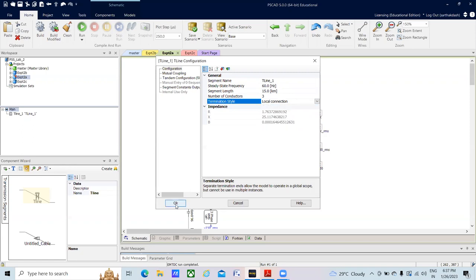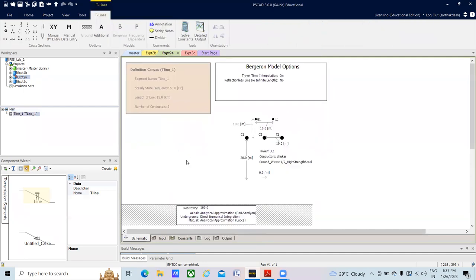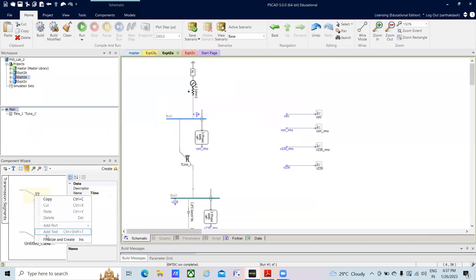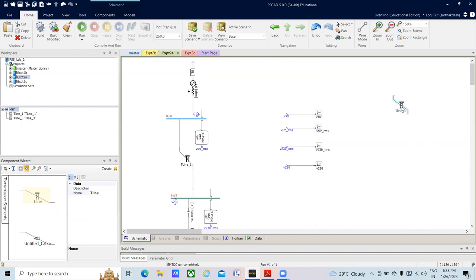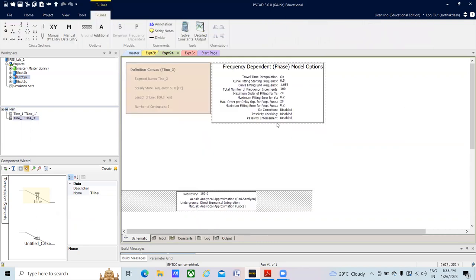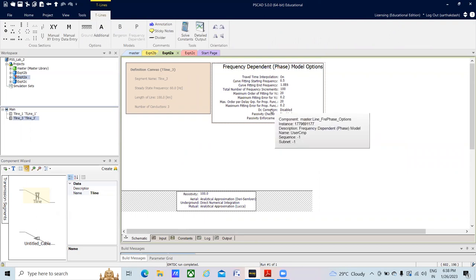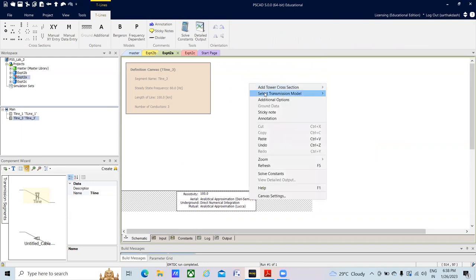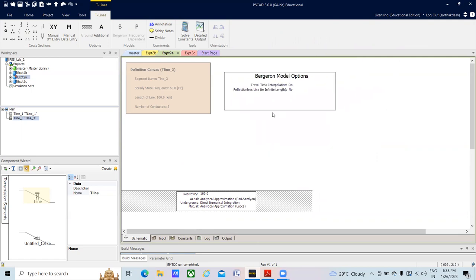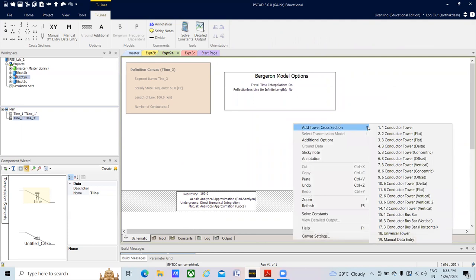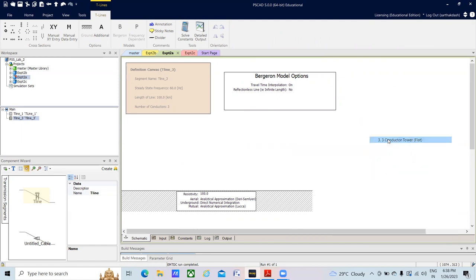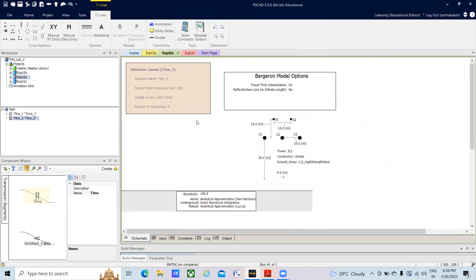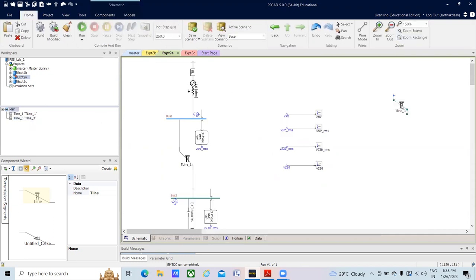Double-clicking on the transmission line, you will find Bergeron and model options. If you want a Bergeron model, click on the frequency dependent model, press Delete, then right-click and select Transmission Model. Select the Bergeron model and place it. You can then add a tower cross section — for example, a three-conductor flat tower. Click on it and place it. In this way you can model the transmission line.